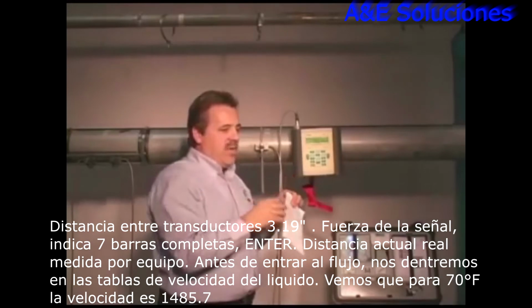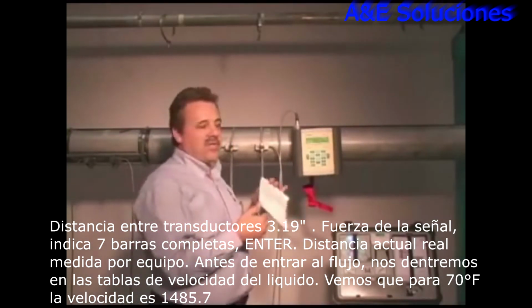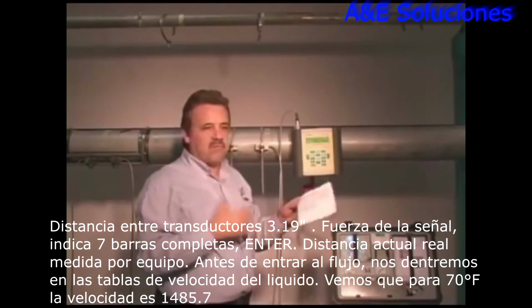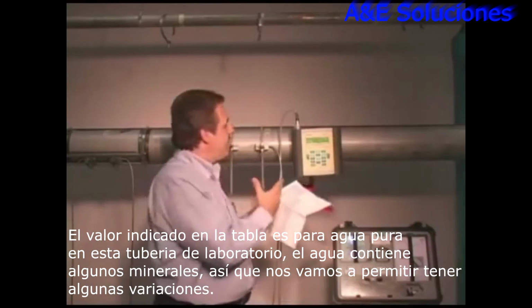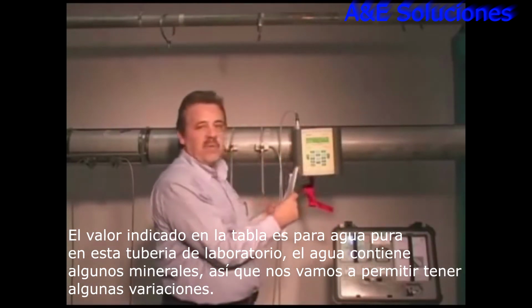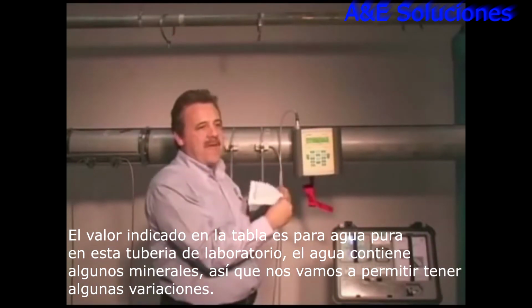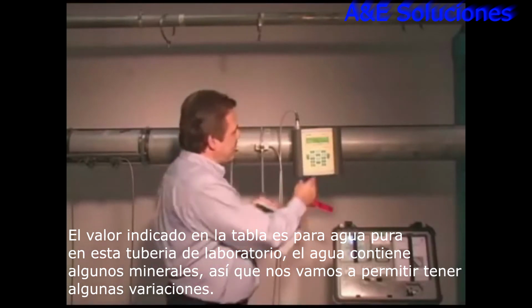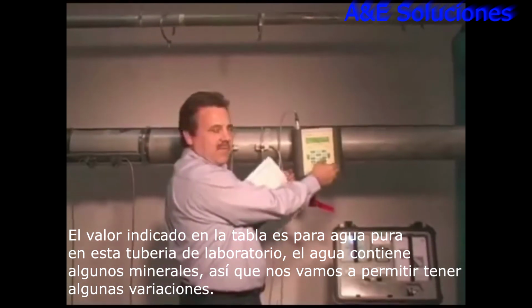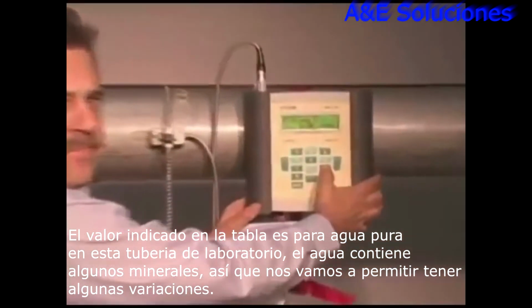Now we know what the sound speed of water should be. We know what it should be at 70 degrees, and we're going to look to see that that's the sound speed we get. If we don't, then it means that we did something wrong. Now I'm showing you how to get to the sound speed. If you want to zero in on the meter here again.